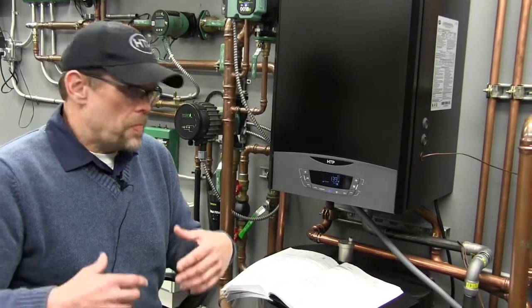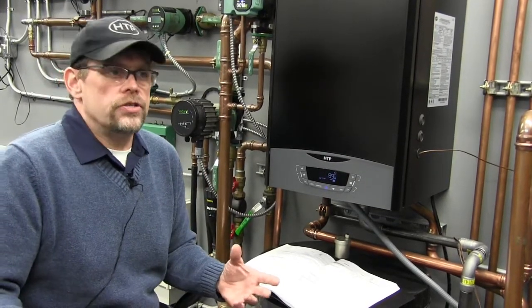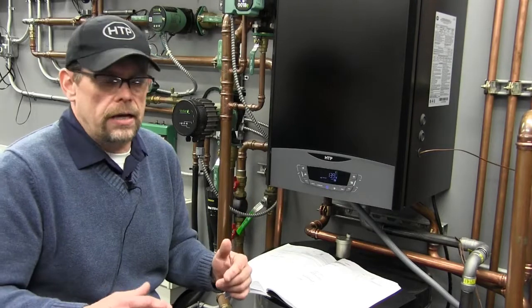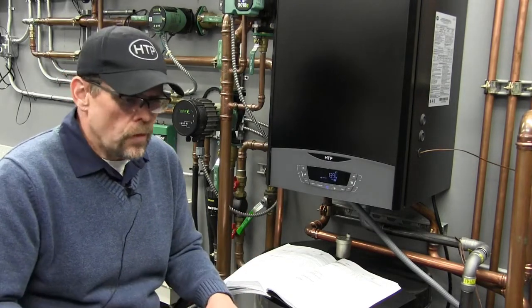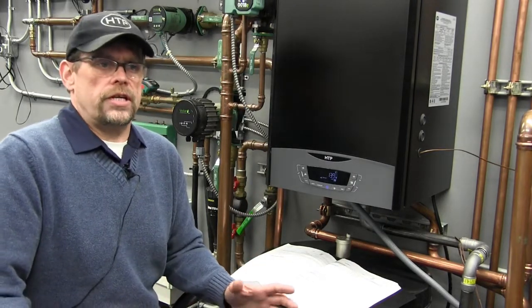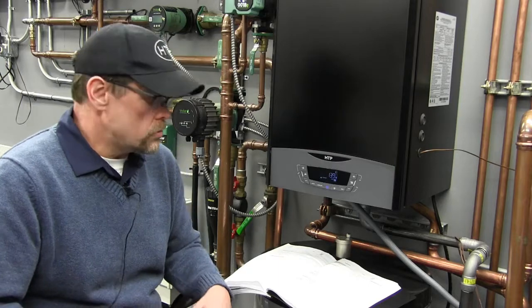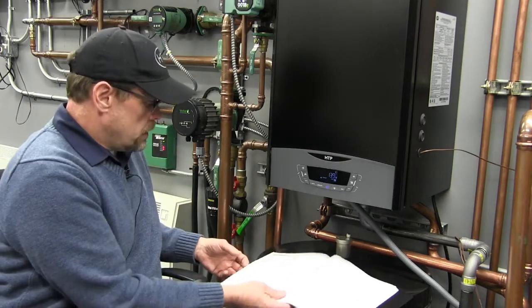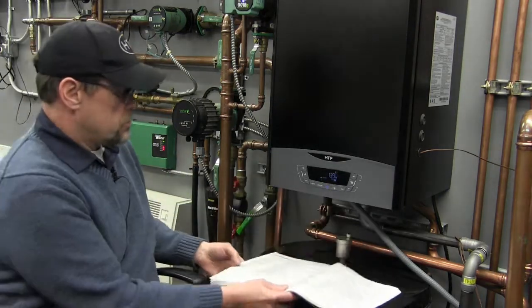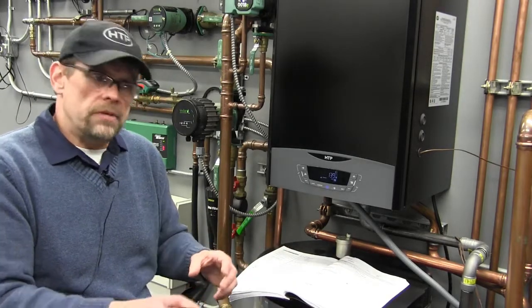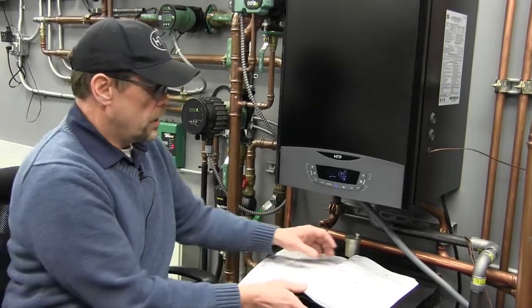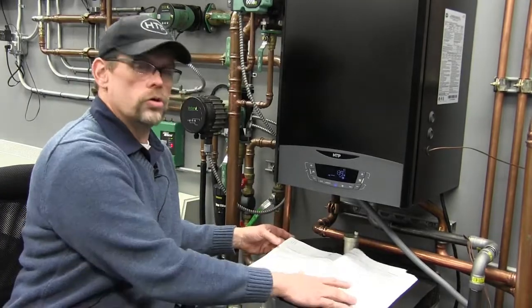Again, in 99% of applications, in residential applications for sure, the 68 degree warm weather shutdown default is going to be fine. However, we do have the ability to go in and fine tune. In essence, the quick access is tuning in our boiler, but sometimes we need to fine tune it a little bit, and that fine tuning can be done through the full menu.